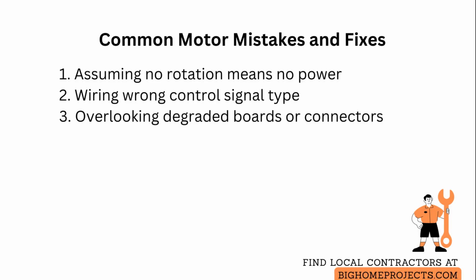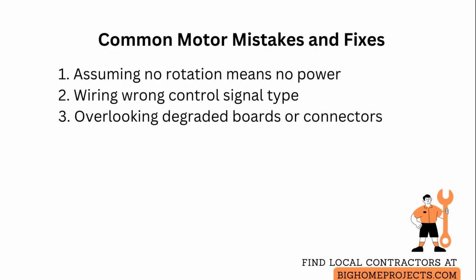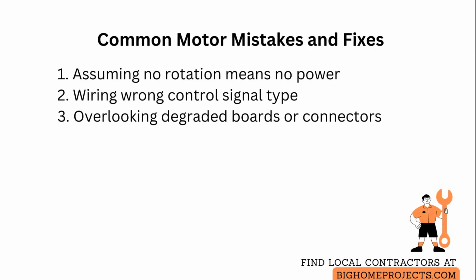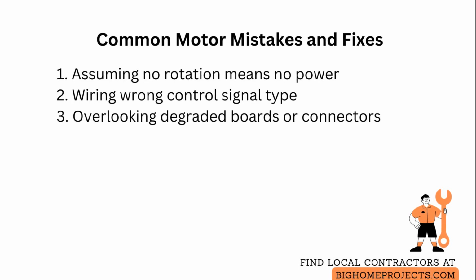A common mistake is assuming that absence of motor rotation means no power at the motor. Verify both the high-voltage feed and the low-voltage control call, and if the control call is present with no rotation, replace the control module or motor.